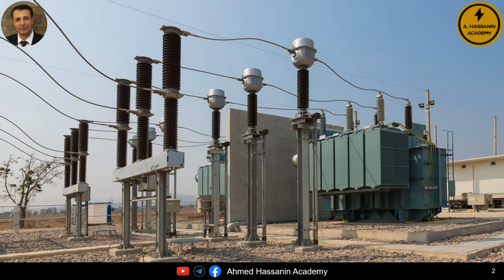In the name of Allah, if we have a power transformer in a substation and this transformer was disconnected for maintenance work, for example, and after completing this maintenance, it is required to reconnect the transformer, energize it, and return it to service. We may find, for instance, that when the transformer is energized, it trips immediately. Naturally, we find that the protection device responsible for tripping the transformer is the differential protection relay.